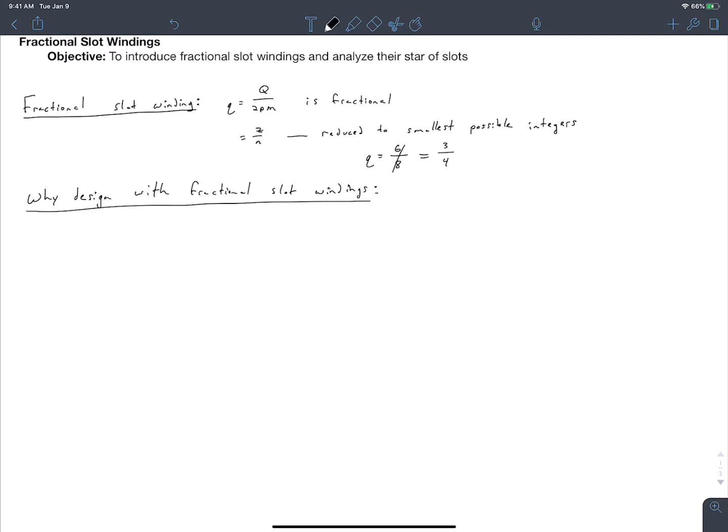Fractional slot windings make our winding analysis and design more complicated, so why do we use them? One reason is that we get more flexibility in selecting our number of slots or number of pole pairs. You might have a situation where somebody already has made a stator lamination and you're asked if you can use it with a rotor that has a different number of pole pairs than was originally intended.